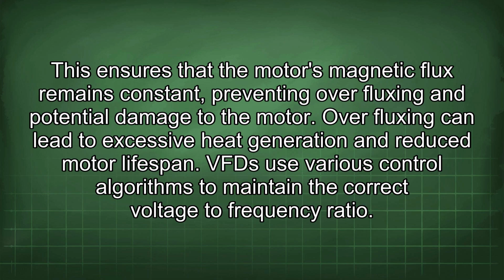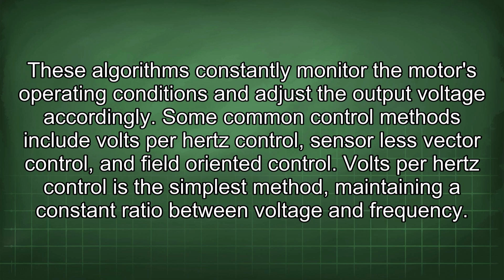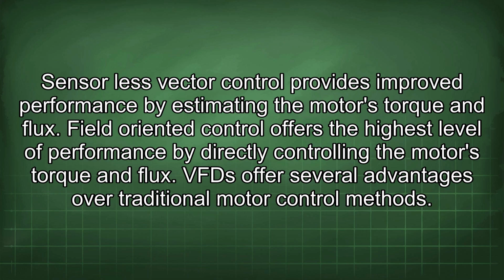VFDs use various control algorithms to maintain the correct voltage to frequency ratio. These algorithms constantly monitor the motor's operating conditions and adjust the output voltage accordingly. Some common control methods include volts per hertz control, sensor-less vector control, and field-oriented control. Volts per hertz control is the simplest method, maintaining a constant ratio between voltage and frequency. Sensor-less vector control provides improved performance by estimating the motor's torque and flux. Field-oriented control offers the highest level of performance by directly controlling the motor's torque and flux.